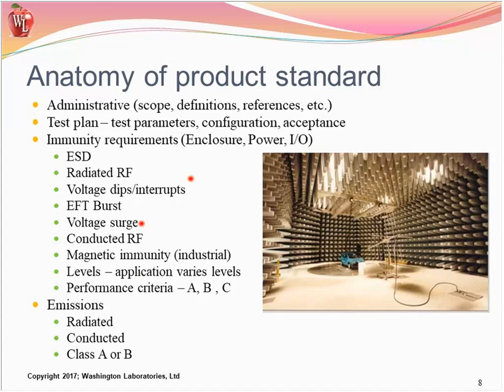The EFT burst, where do we apply it - to the enclosure port, usually for fields of some kind, the power lines or the I/O ports. Could it be a power port AC or DC? It could be applicable to one and not the other. It also calls out emissions for radiated and conducted, and defines it as Class A or B.